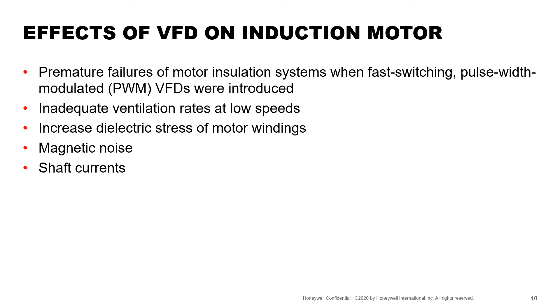The chopped DC voltage from a VFD can bring about some undesirable effects on a standard AC induction motor. A VFD sends brief pulses of voltage that are higher than what the motor usually is exposed to. This can stress the motor winding insulation and cause it to break down. When the motor is run at speeds lower than 60 Hz, its temperature may rise as the shaft mounted fan is providing less cooling.